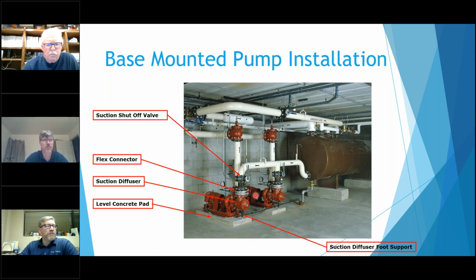But if the pipe isn't properly supported, because sometimes it's hard to get some of those pipe hangers in there, I know that. I've seen so many installations where they're trying to jam so much stuff into one room. You really want to have the support here so you don't have the weight of this water, the pipe, and these fittings pulling down and cracking the volute. So it's really important to have that support foot underneath that suction diffuser.